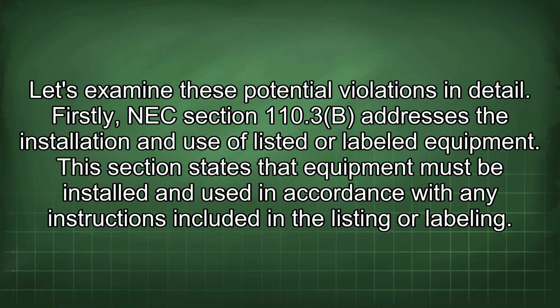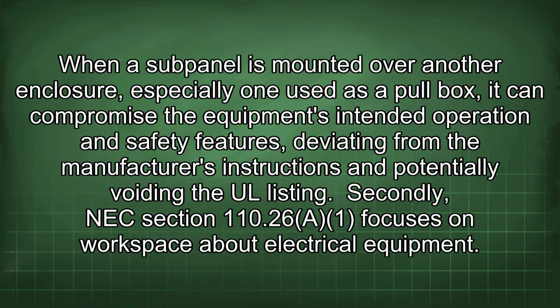Firstly, NEC Section 110.3(B) addresses the installation and use of listed or labeled equipment. This section states that equipment must be installed and used in accordance with any instructions included in the listing or labeling. When a subpanel is mounted over another enclosure, especially one used as a pull box, it can compromise the equipment's intended operation and safety features, deviating from the manufacturer's instructions and potentially voiding the UL listing.